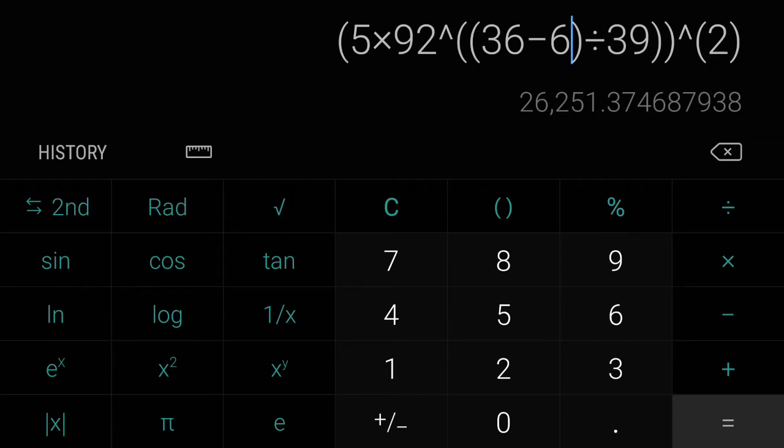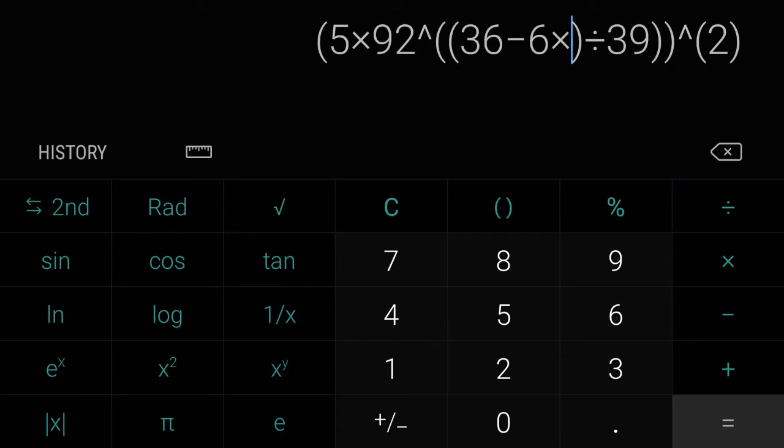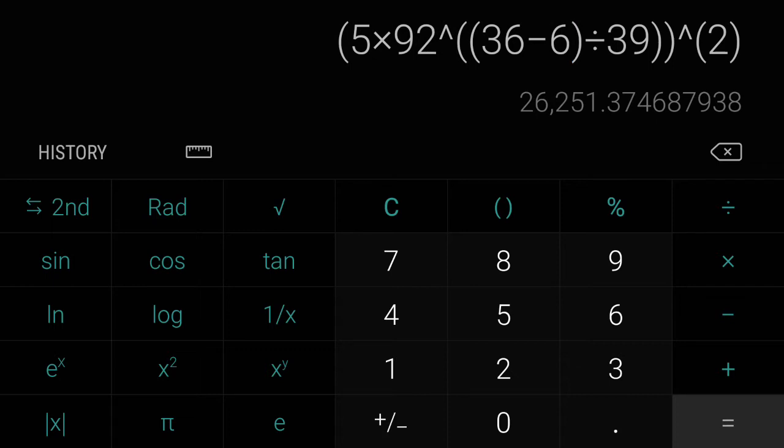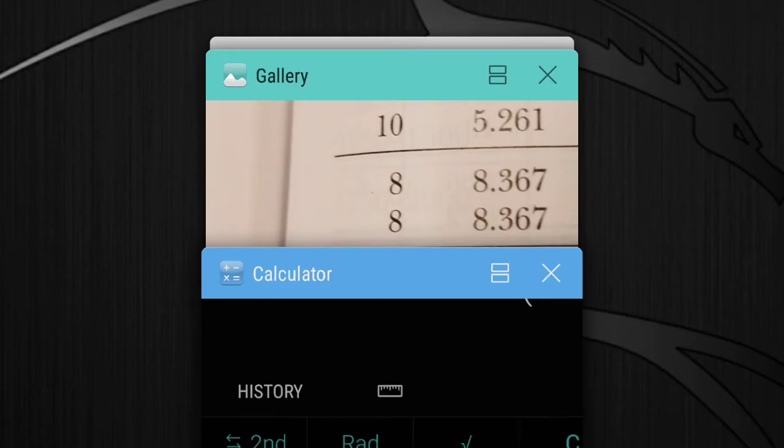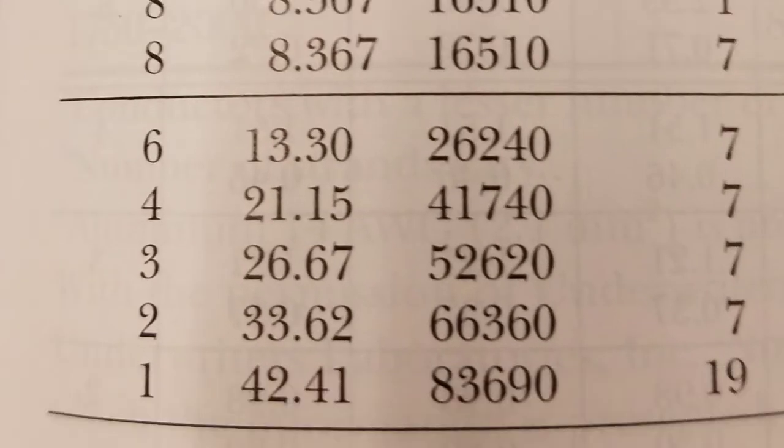So I'll go to my equation and we'll change the 12 gauge to 6 gauge and you have 26,251. Now to properly round this to the nearest ten I would say that it's 26,250, but if we check the National Electric Codebook, 6 gauge, 26,240.